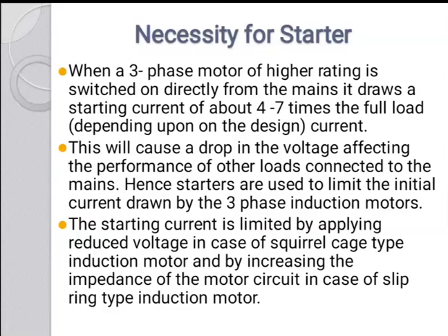That current it will take only during the starting. But when the motor gradually picks up and is loaded, the current will come down to its full load current. This will cause a drop in the voltage, affecting the performance of other loads connected to the main supply. Hence starters are used to limit the initial current drawn by the three-phase induction motor.